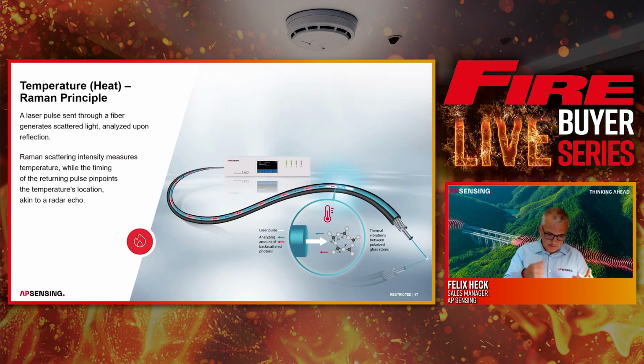The sensor cable must be connected, of course, to our controller, as you can see here, and the controller will send out a laser pulse into the fiber, and by the scattering of the molecules on a certain position along the whole sensor cable, we measure the temperatures along the whole sensor cable. If at a certain position the temperature passes a certain pre-adjusted temperature, then an alarm will be triggered. We will see this later on. An alarm will be triggered, and then the linear heat detector will trigger the alarm for the fire panel and then issue a fire alarm.